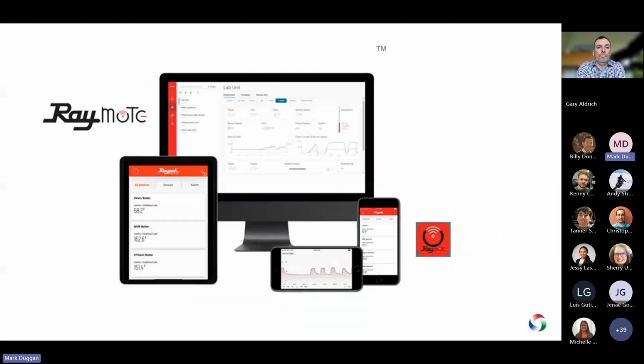So if you have a maintenance crew that's got several different boilers they're in charge of, they can add them all to their Raymote account and basically review all of it that way. The other nice thing about this is if you're having a weird technical issue where the boiler's locking out, let's say in the middle of the night when nobody's in there, then the maintenance guy goes there, it runs all day, no problems, and it locks out again at night. You're able to pinpoint what's actually happening when it locks out. You can look at all those parameters.